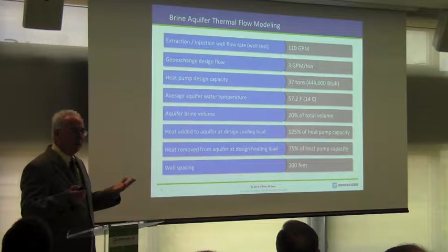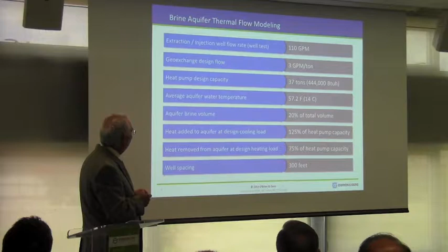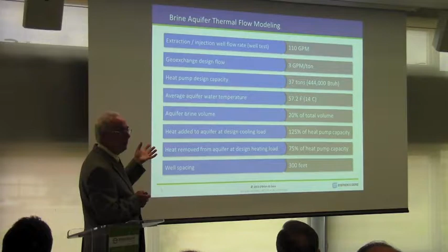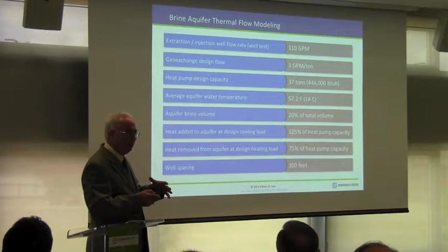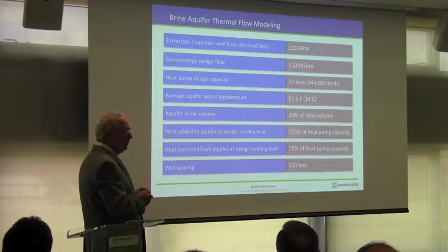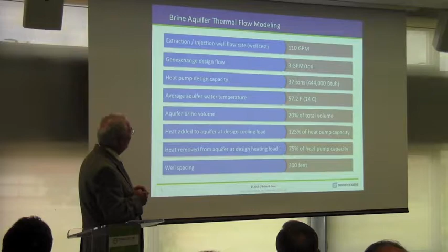For a geo-exchange, 3 gallons per minute per ton, that's a 10-degree delta T across the heat exchanger. We thought that looked reasonable, and that gave us a heat pump design capacity of a little less than 40 tons, which was enough to do not all the pipe lock building, but a reasonable portion of them. I think Sam's going to talk about what portion that was. The average aquifer temperature is 57.2 degrees F over the course of the year. And we assumed a volume at that location of about 20% water, with the rest being solid.